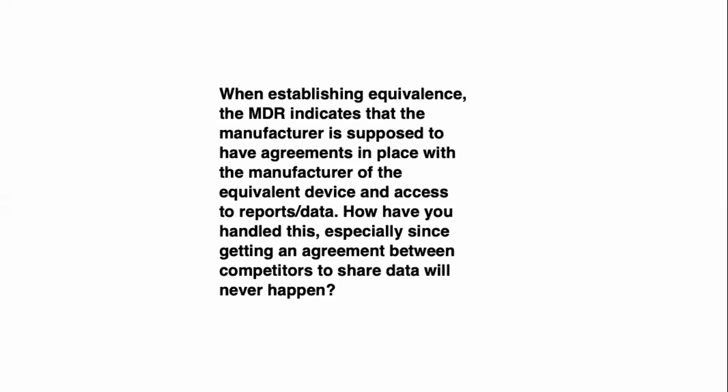When establishing equivalence, the MDR indicates that the manufacturer is supposed to have agreements in place with the manufacturer of the equivalent device and access to reports data. How have you handled this, especially since getting an agreement between competitors to share data will never happen? Well, it's a long question with a very short answer. In all of the CERs that we've written for many manufacturers, we have never handled it.